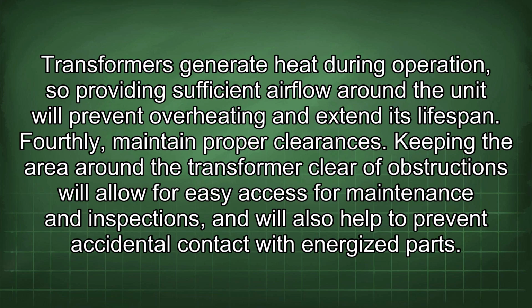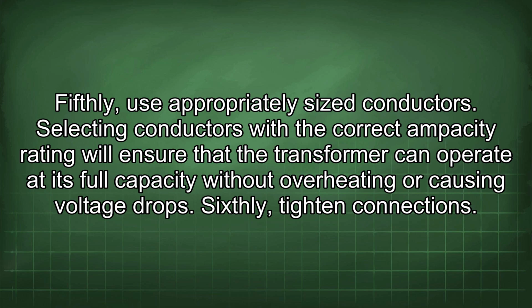Transformers generate heat during operation, so providing sufficient airflow around the unit will prevent overheating and extend its lifespan. Fourthly, maintain proper clearances. Keeping the area around the transformer clear of obstructions will allow for easy access for maintenance and inspections, and will also help to prevent accidental contact with energized parts. Fifthly, use appropriately sized conductors. Selecting conductors with the correct ampacity rating will ensure that the transformer can operate at its full capacity without overheating or causing voltage drops. Sixthly, tighten connections.